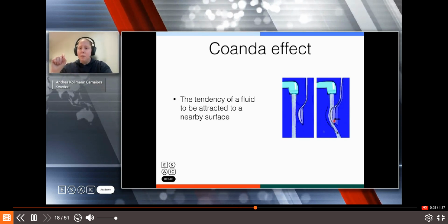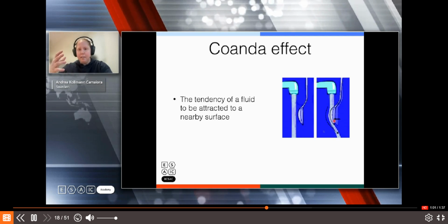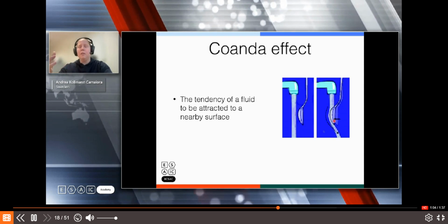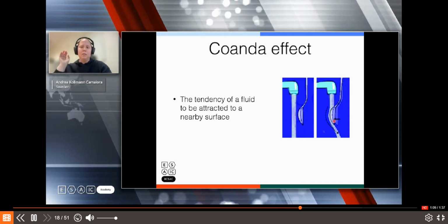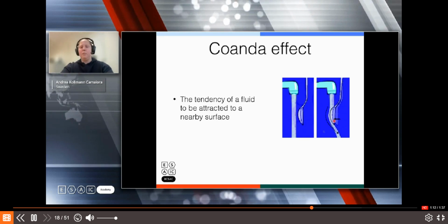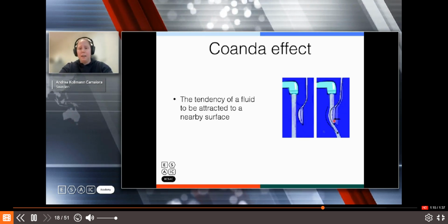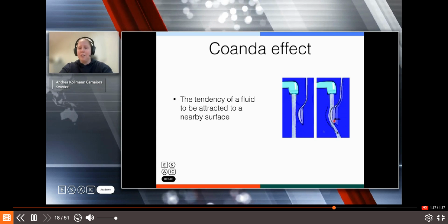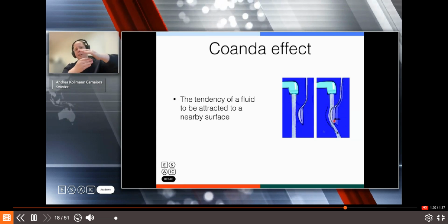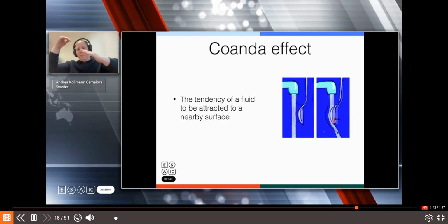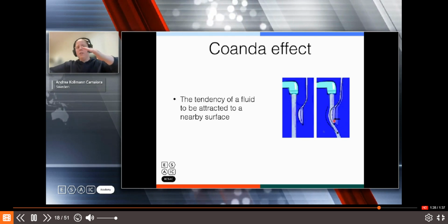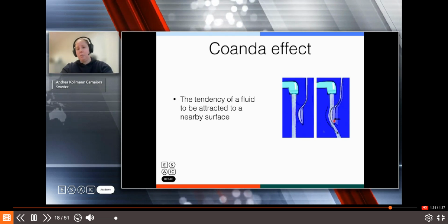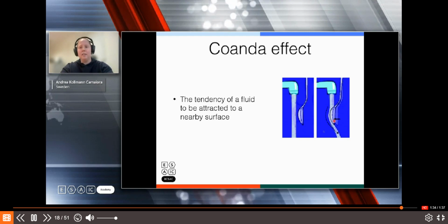In the anesthesia equipment class, I'll be talking about the unidirectional valves, when you have your breathing system so that the inspiratory limb and the expiratory limb have valves. Well, previously they had valves. Now they rely on the Coanda effect to have different angles. So if the air is coming this way, when the patient is expiring, it will follow a certain angle, and by modifying these angles using the Coanda effect, you have exactly the same effect as unidirectional valves.